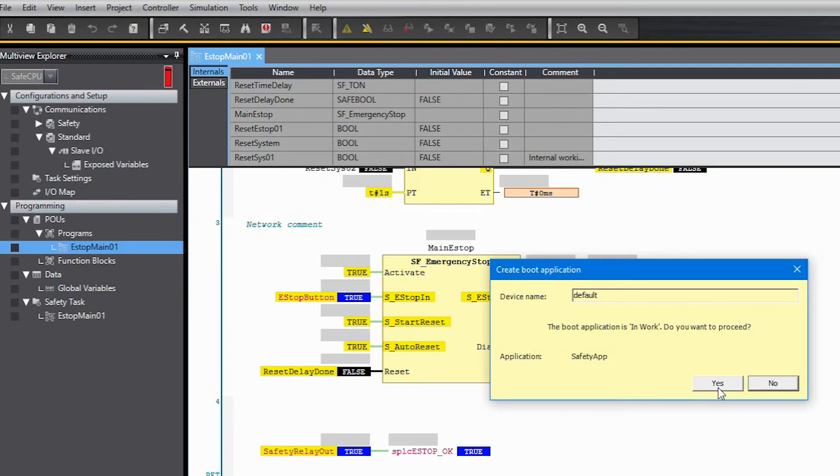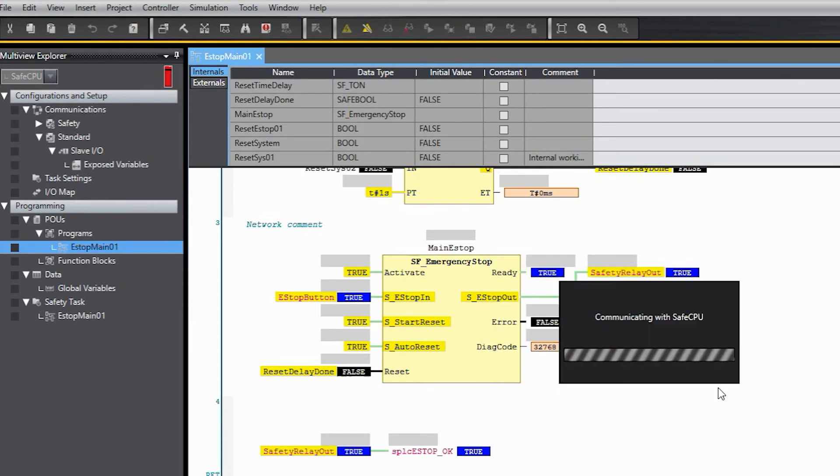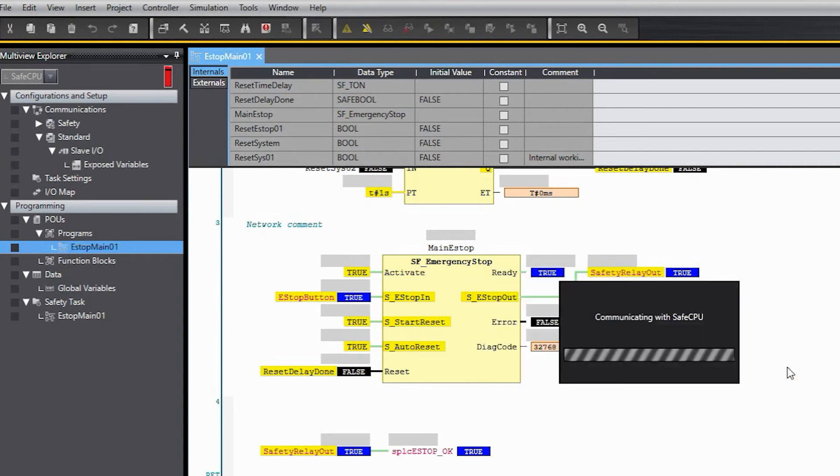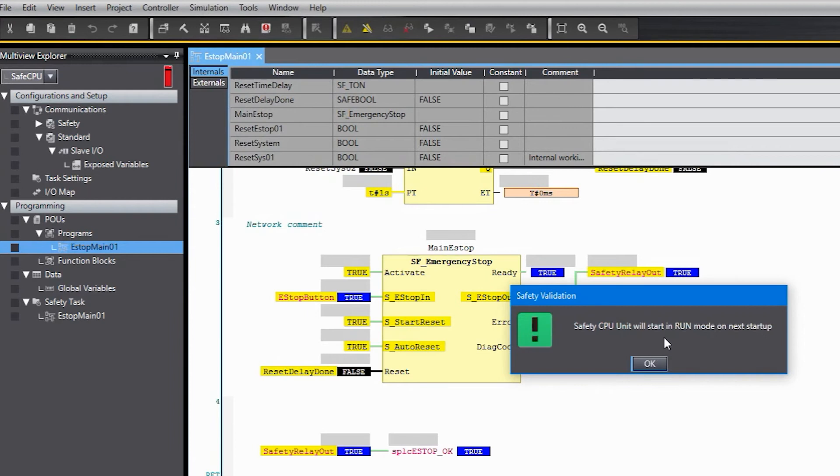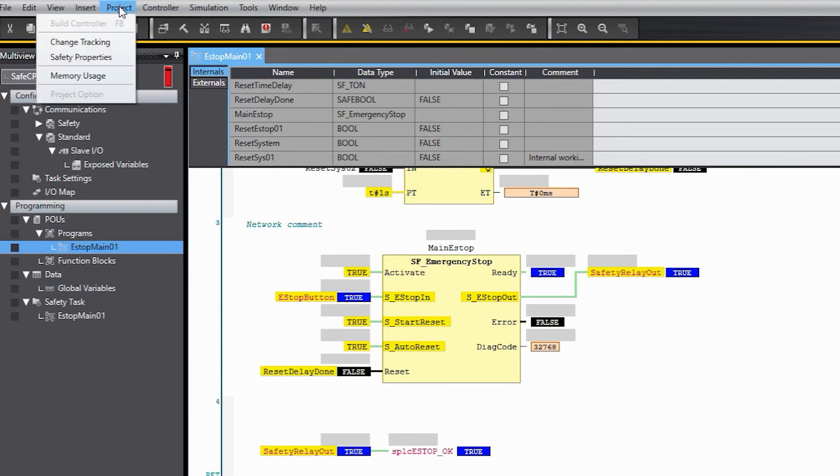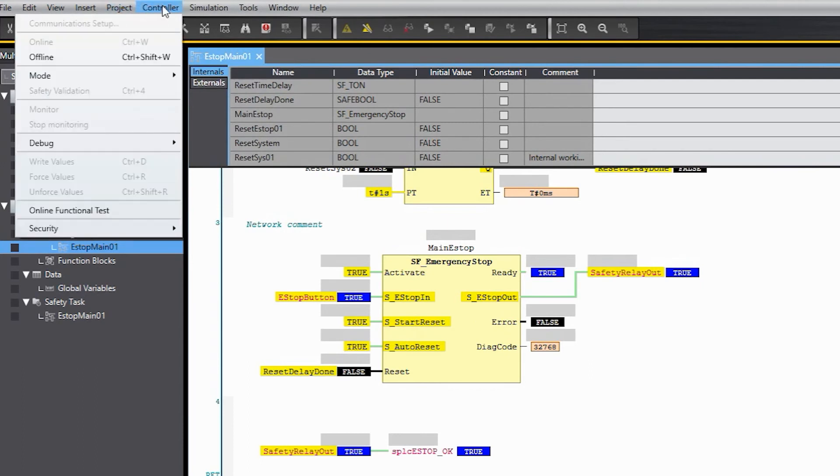And we just say yes we're going to validate it. It's going to ask a few questions here. So now it says the safety CPU unit will start in the run mode on the next startup. And if I look at the LEDs on the front of the CPU you'll see that the debug LED is still illuminated. So even though we validated it and finished that process it's still in debug mode.